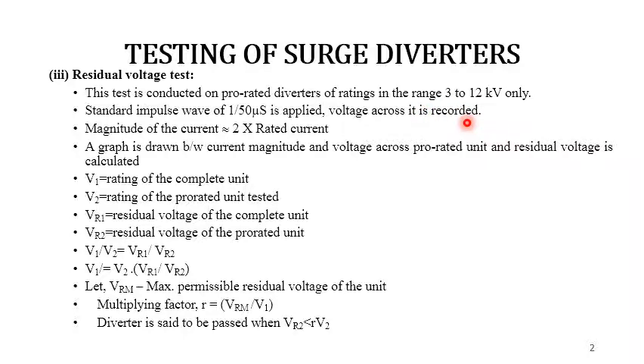The magnitude of the current is approximately 0.5, 1 and 2 times the rated current. From this, that is the oscillogram, a graph is drawn between the current magnitude and the voltage across a prorated unit, and the residual voltage is calculated. From this graph, the residual voltage corresponding to the exact rated current is obtained.